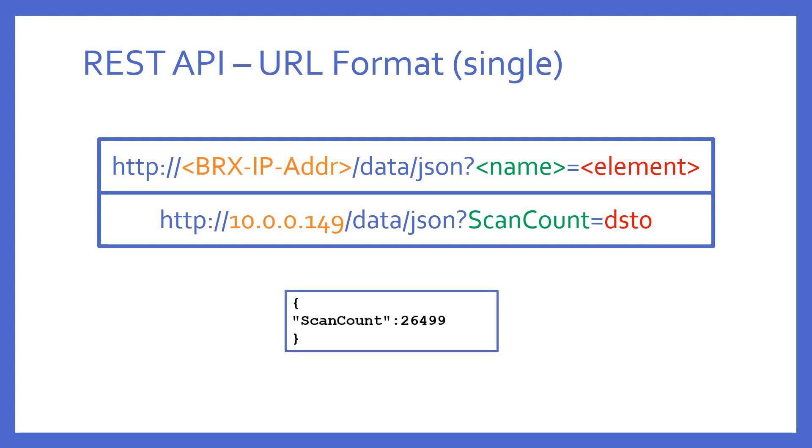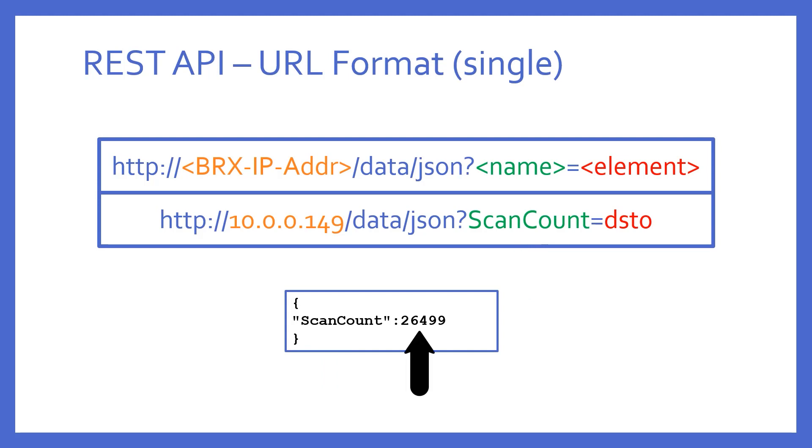This. Notice the data value in DST0 is the value portion of a name-value pair called ScanCount. It's presented as a single JSON object, properly contained in curly braces. ScanCount is the name I chose to call it. Also, even though this value is constantly changing, this URL will only give the value of DST0 that was read at that moment. It will not continually update unless you keep hitting the refresh button in your browser.